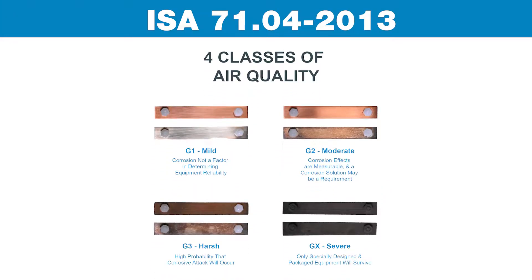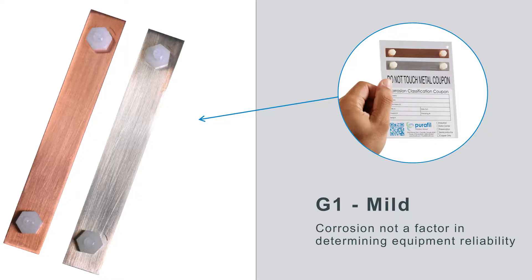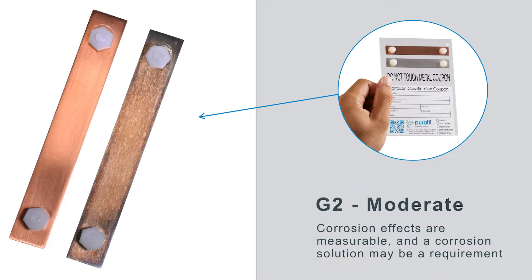There are four classes of ISA 71.04-2013 corrosivity levels. G1 – Mild. Corrosion is not a factor in determining equipment reliability. G2 – Moderate. Corrosion effects are measurable and corrosion may be a factor in your environment.